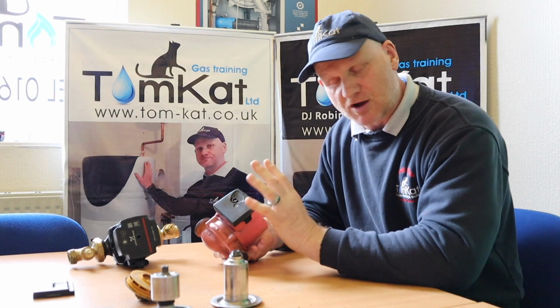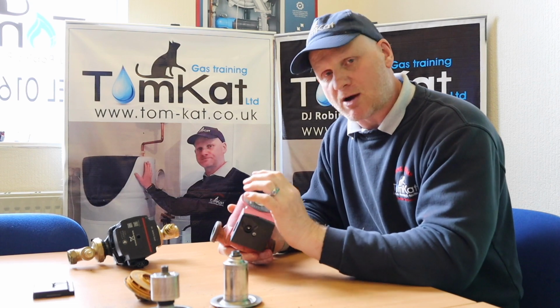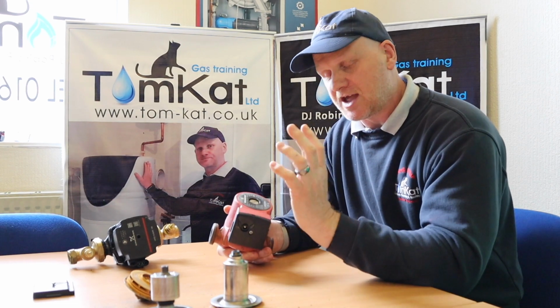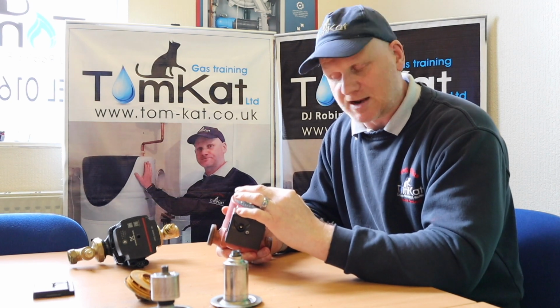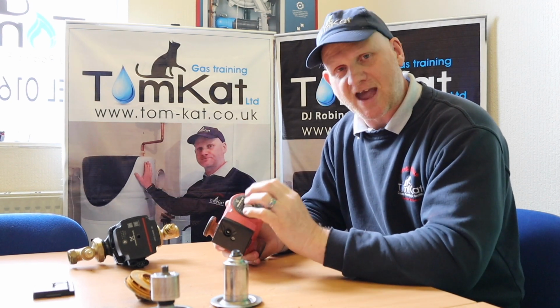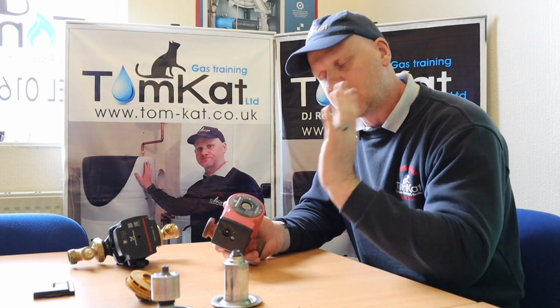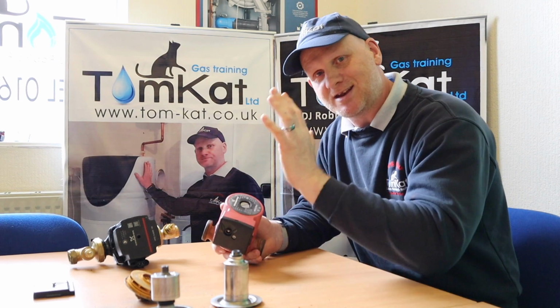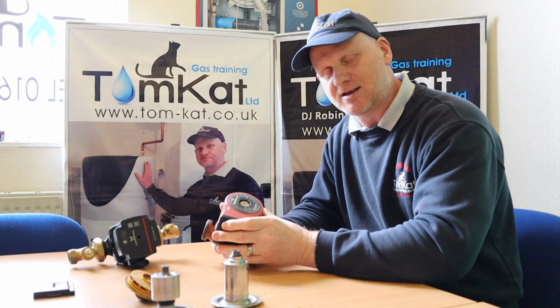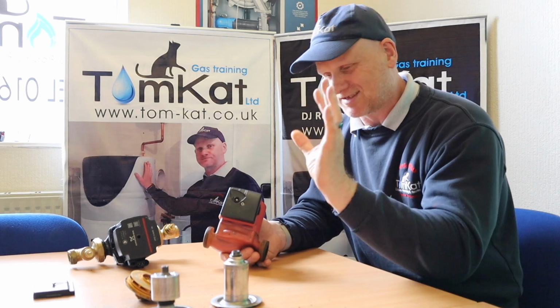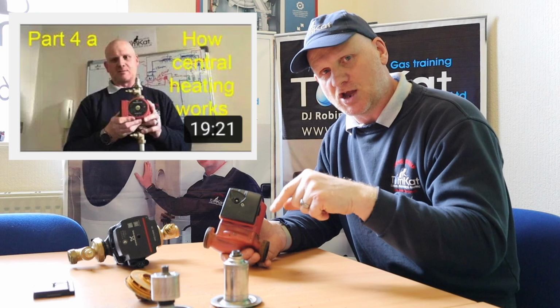Another fault is it's not running and it's got red hot, which we talked about. That could be it's got full of air, it's cavitated, it's not pumping any water. Again, you can open the bleed screw and if you get air, steam, water coming out of there, then you can screw the screw back in and it should run. So they're the common faults. If it's not doing anything, if it's freezing cold, then it's every chance that the pump might have burnt out or one of the controls isn't working, and that's a little bit more in depth. If you look at our video on the history of central heating, I go into pumps that way in a little bit more depth. So that's a look at the UPS old pumps.